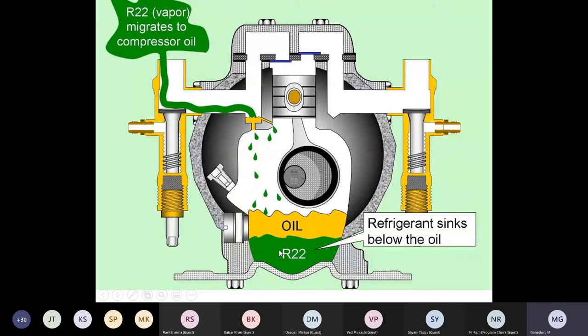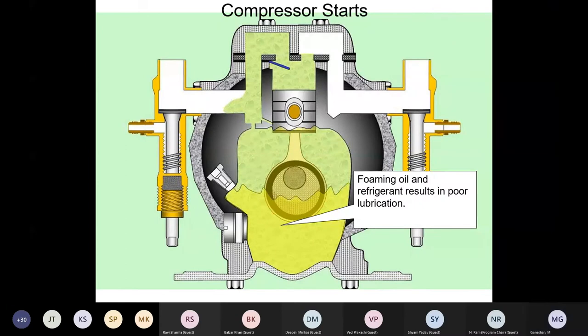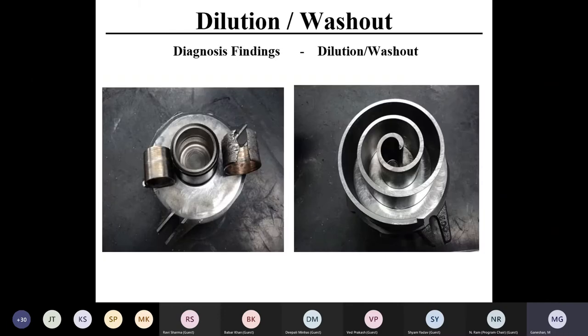So whenever we start the compressor next time, along with the liquid, the refrigerant and oil both together, it will just foam. That is what you are seeing in the sight glass, this foaming. When both mix and come back into the compressor, it can damage the whole thing, because it is completely liquid and oil put together coming back into our system. When the liquid is there in the compressor, this can damage it.